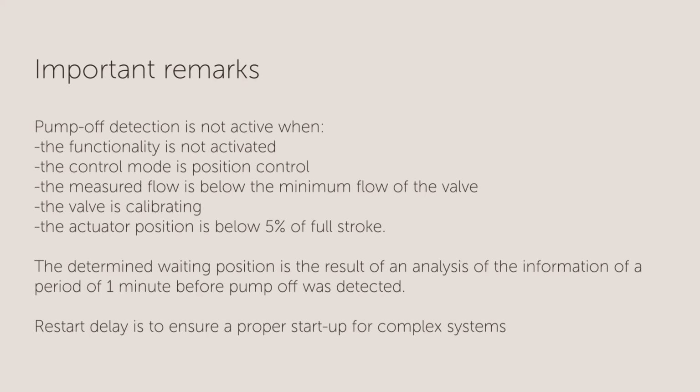Pump off detection is not active when the functionality is not activated. The control mode is position control when the measured flow is below the minimum flow of the valve, when the valve is calibrating, or when the actuator position is below 5% of the full stroke.